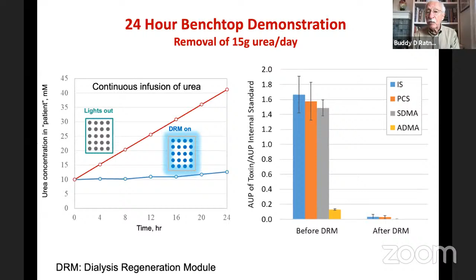On the right, we're looking at some of the other toxins that also have to be removed. And interestingly, this UV photocatalytic system pretty much burns up any organic, and so that has a number of advantages. We know for this whole system, that's how we're going to get rid of urea. We also need improved biomaterials. Again, a patient wearing this device long-term, we can't be replacing the tubing every 4 hours, can't be replacing the membranes, and the patient can't be continuously anticoagulated. We have to have tubing, membranes, blood components that are much more resistant to fouling and to blood elements.